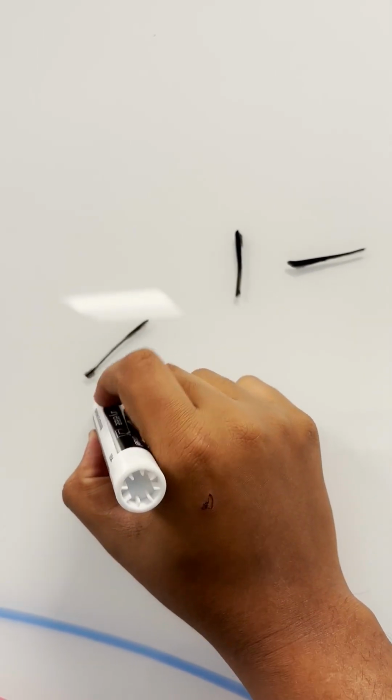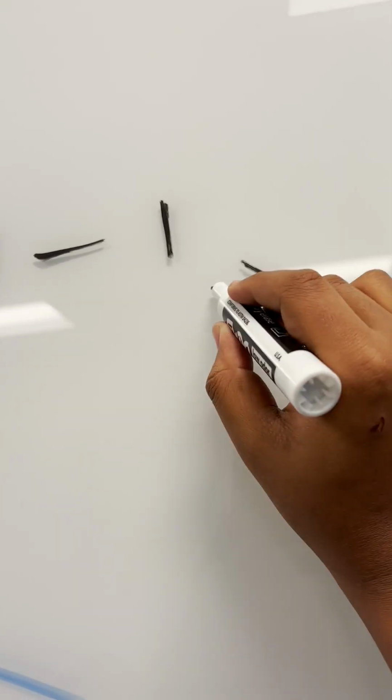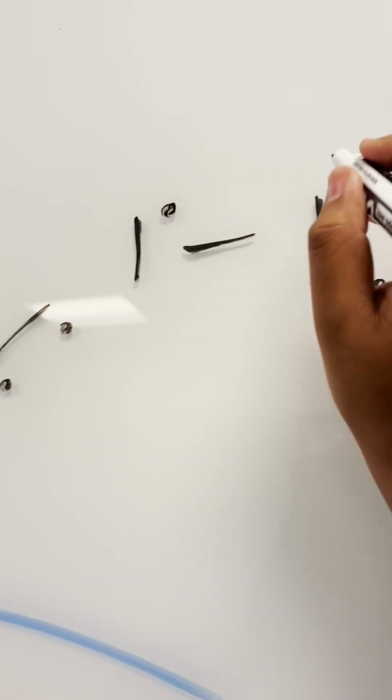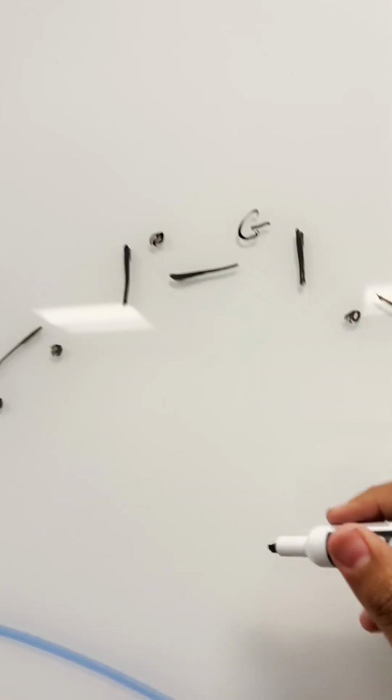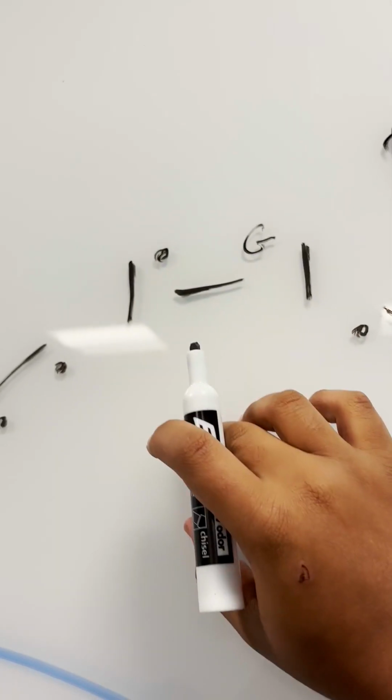And the color coding here is black and black, and the color coding here is black and black on both ends, just like you have here, right? But then on one end it's black, but on this end it's gray. You then have what's known as a polarity issue because it's crossed on one end.